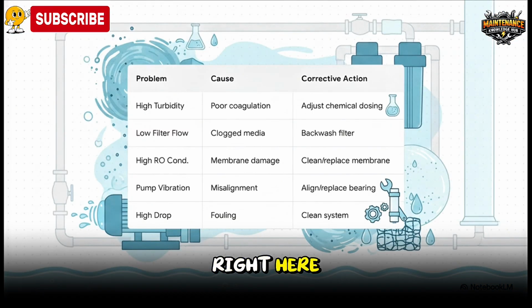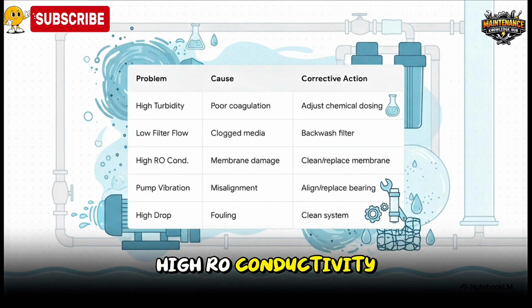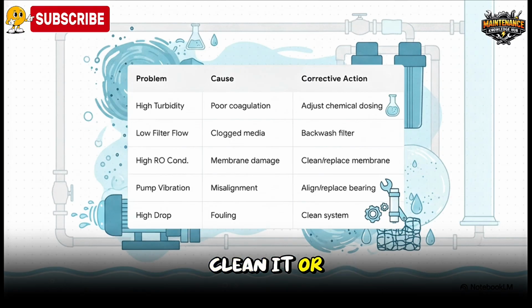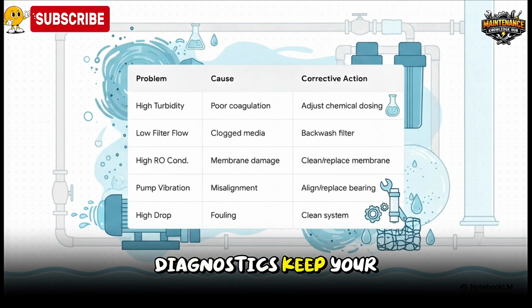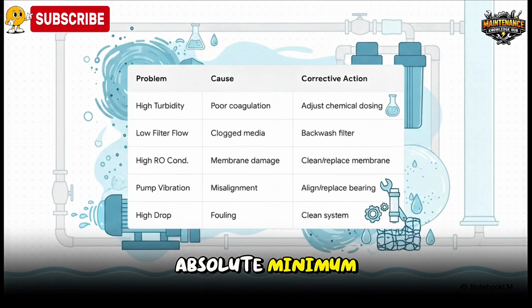Now, this right here is a fantastic cheat sheet for your operators. It directly links the symptom to the root cause so they can act fast. High turbidity, you've probably got poor coagulation. Time to adjust the chemical dosing. Pump vibration, that points straight to misalignment or bearing wear. High RO conductivity means membrane damage. Clean it or replace it. Fast diagnostics keep your downtime to an absolute minimum.